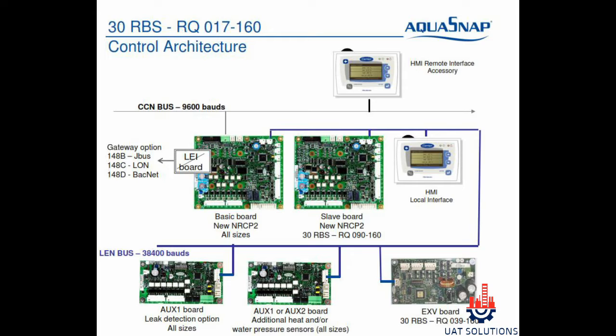Electronic modules used for this chiller are as shown. NRCP2 module is the main processor board and it can control two compressors in one circuit. If there are two circuits or compressors more than two, then another NRCP2 module is installed as a slave board.